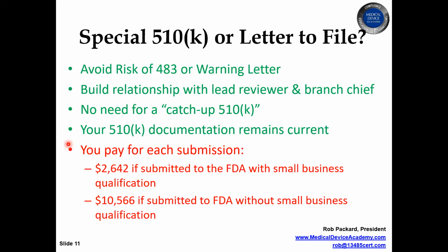I know one client that had to do a catch-up 510K after 40 years of changes. Really tough situation to be in because some of the documentation was very old and it was very hard to show how the current device was similar to the original device, even though it was very similar to the last change they made. Each change was a minor modification, but after 40 years of doing that, your original device is so different from where you are today that you need a catch-up.